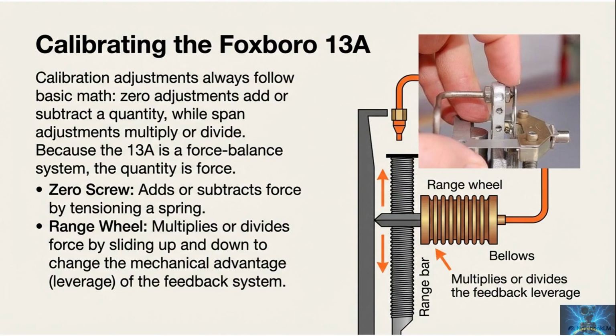Calibrating the Foxboro 13A: calibration knobs usually fall into two categories, zero shifts and span changes. The zero screw adds or subtracts force by adjusting spring tension, shifting the output up or down. The range wheel changes leverage by sliding the linkage point, changing the mechanical advantage of the feedback system. After each adjustment, you recheck because the loop is interconnected and everything influences balance. The big idea is that you are calibrating a force balance machine, not a digital number.